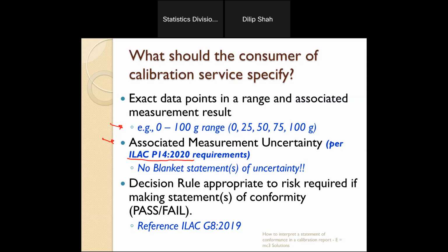A lot of accredited labs do not calculate the measurement uncertainty properly. That doesn't do us any good if they don't give you the right information, because we're going to use that to decide our acceptance limits, and if they give us the wrong measurement uncertainty... And that's why the three pillars of measurement, right? The measurement uncertainty that associates the metrological traceability. And then from that, we base our acceptance limits depending on the measurement decision rules we employ. So important to make sure that we do that.